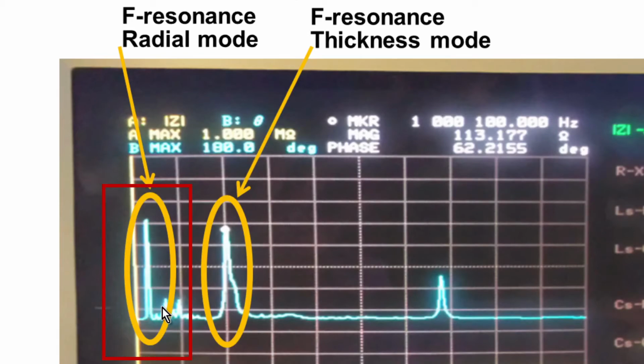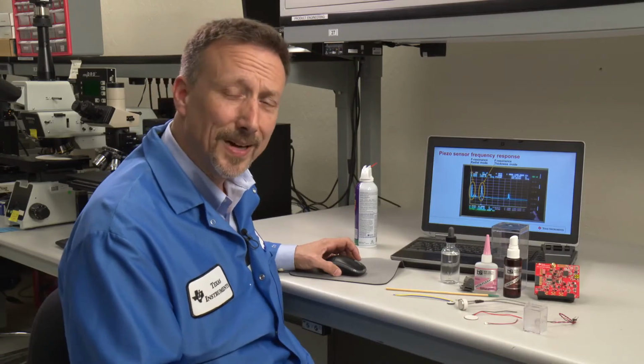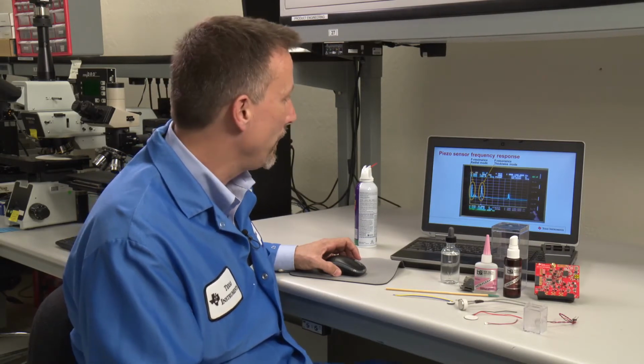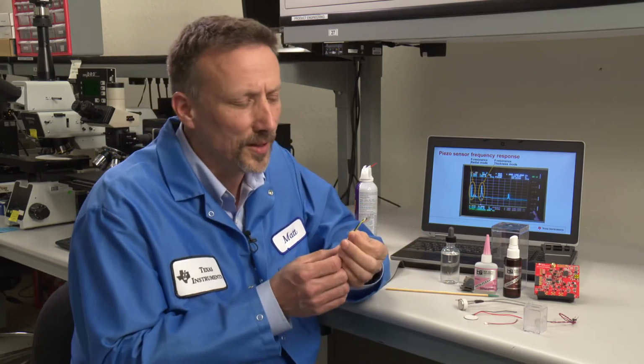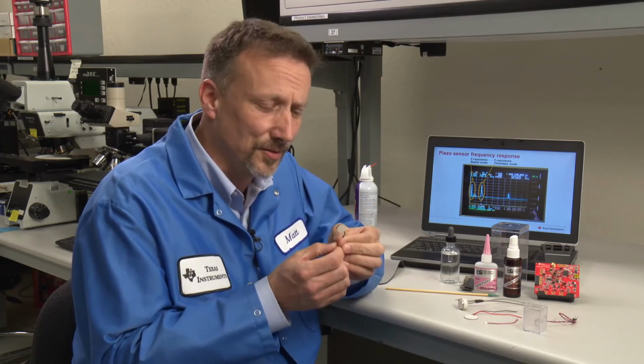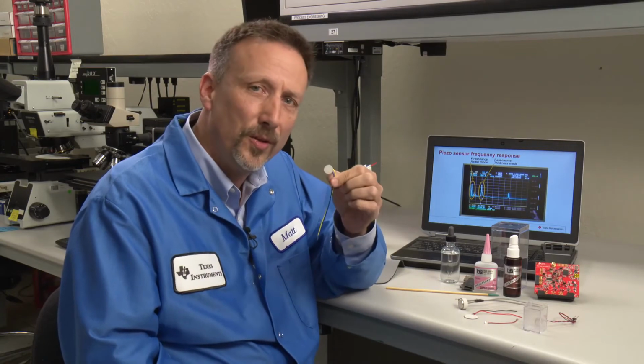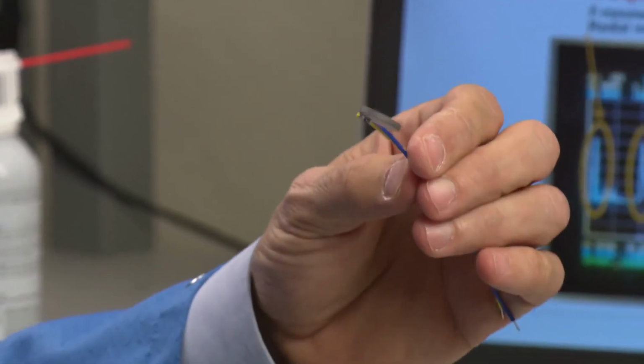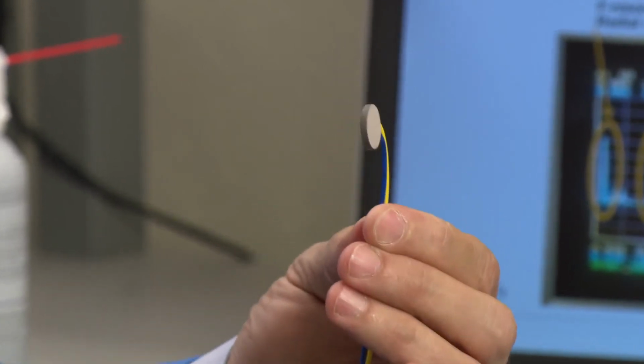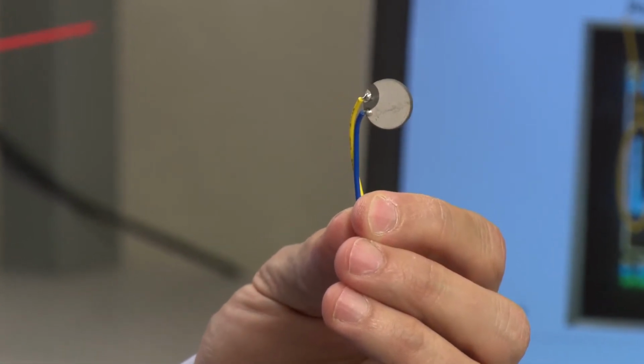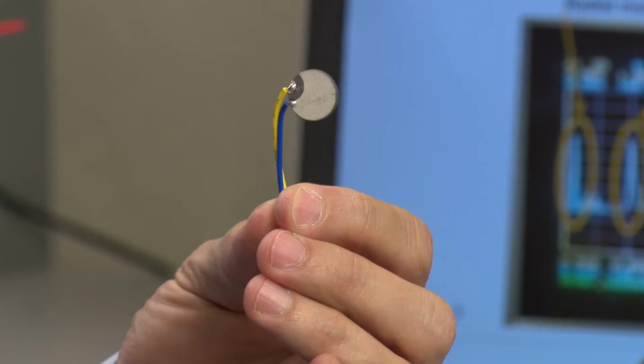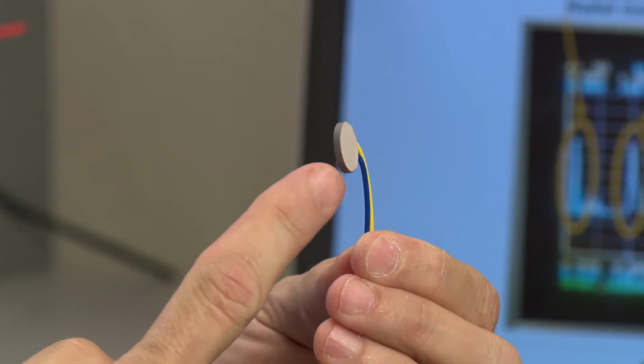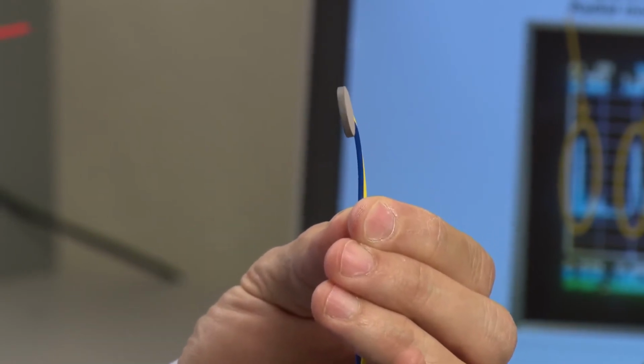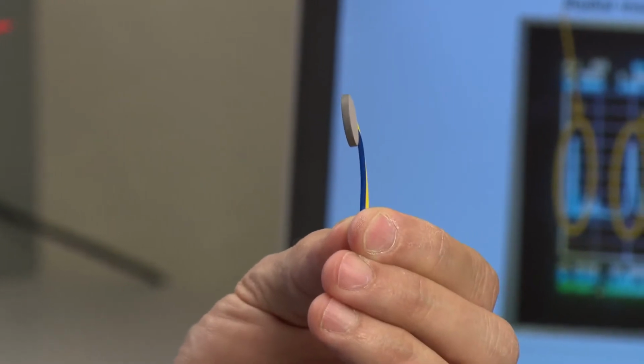Radial resonance is in the radial direction and not useful for this application. Our application here needs resonance in the axial mode. This is also referred to as the thickness mode on some specifications. Going back to our transducer selection, transducers come in different sizes. The size of the transducer will determine a few things about your application. For the demo today, we're going to use this 1 megahertz transducer. Looking closely at this transducer, there's two parameters that we're really going to be interested in. The radial width is going to determine the radial frequency. The thickness of the transducer determines its axial resonance. In this case, this transducer's axial frequency is 1 megahertz.